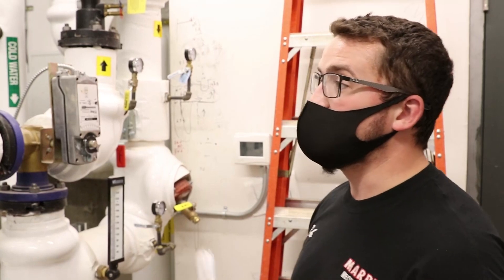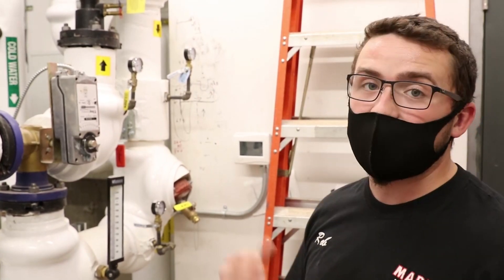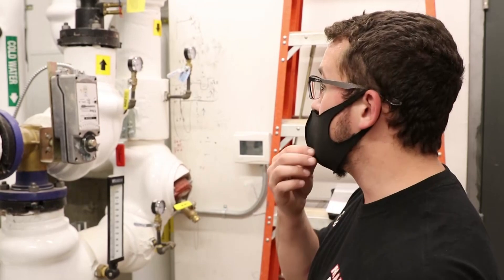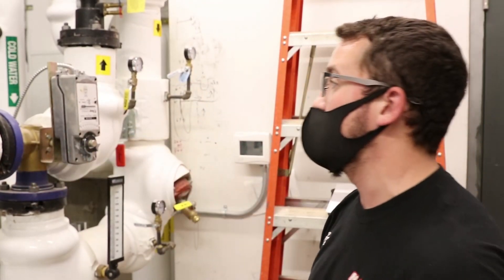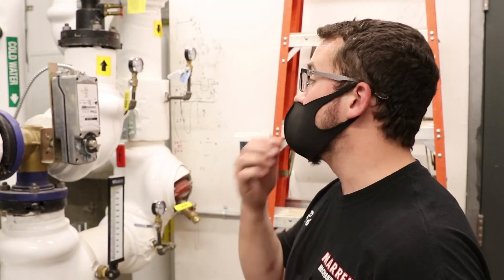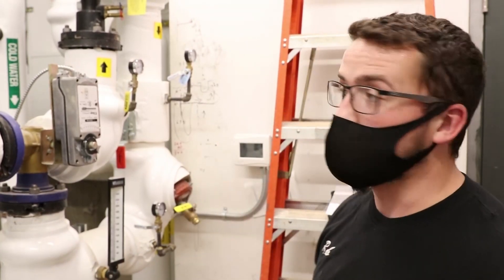And like I said, you'll get symptoms of that as far as the water heater not performing well, a low loss of temperature across the heat exchanger from the supply to the return, and symptoms like that for performance.